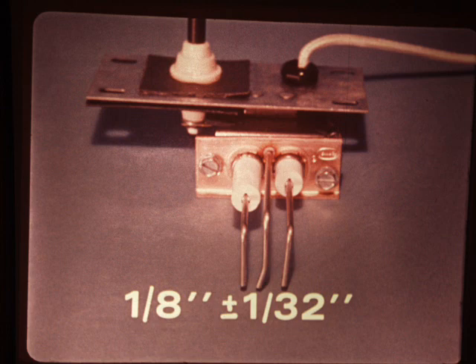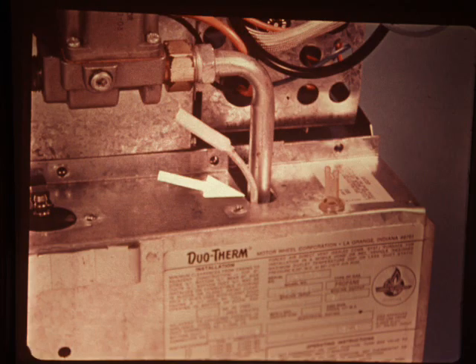Before reinstalling the igniter, you'll want to check the spark gap. It should be 1/8 of an inch plus or minus a 32nd. When reinstalling the front cover, be sure the flame sensing lead is properly located next to the main burner gas line.